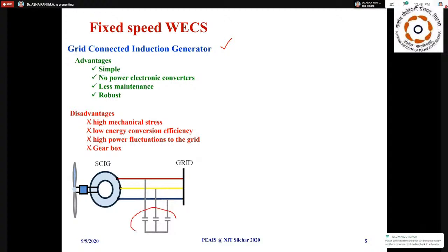You can see there is a capacitor bank. Its role is to provide the reactive power support needed for the machine, because when a squirrel cage induction generator, or any induction generator, is operating, it needs reactive power, or the magnetic flux inside the machine.